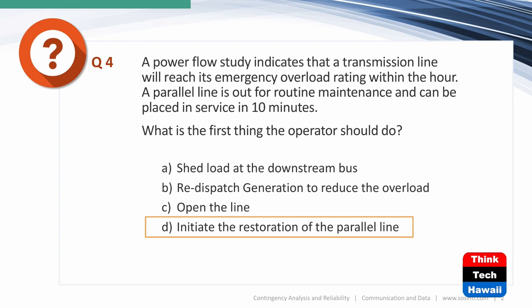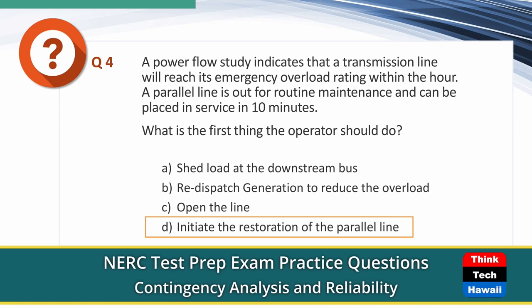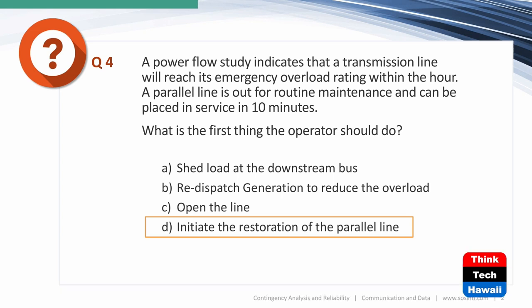Shedding load at the downstream bus would certainly get rid of the overload, but shedding load is always the last resort. You shed load if you had to — usually if you're already in an overloaded state or if continued analysis tells you the line will cascade into a blackout. But right now you're not even overloaded, not until an hour from now — so A is not the answer.